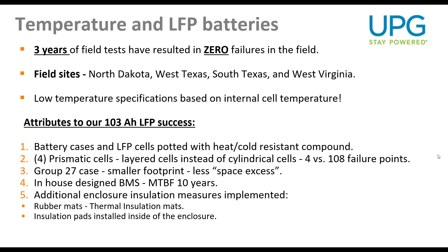Additional enclosure insulation measures have been implemented, and we tell our customers about that. One is underneath the battery, in heat or cold, we put rubber mats for thermal insulation, which helps the bottom of the enclosure from becoming a heat sink or a cold sink. We also use rigid insulation pads installed inside the enclosure that help keep the ambient temperature out and keep the battery warm and running all the time.